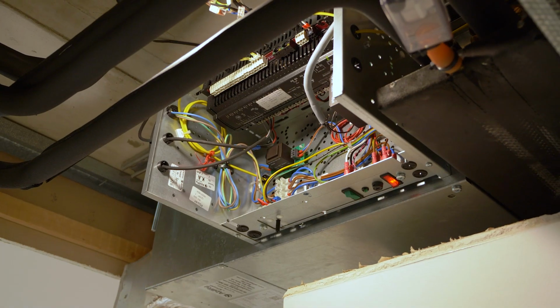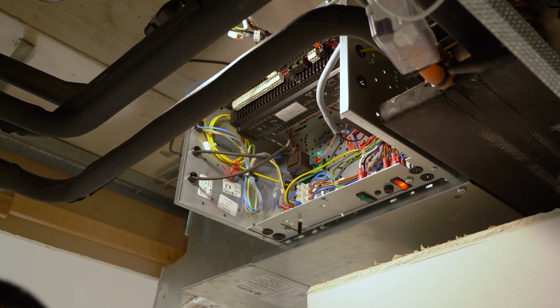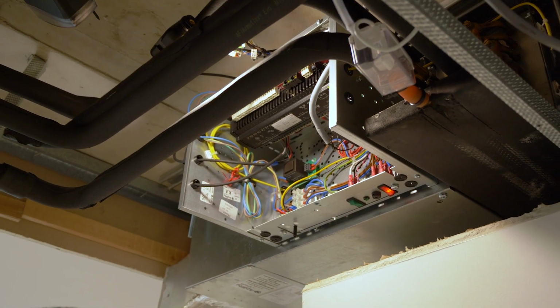One of the obstacles that we encountered on this job was that the old fan coil unit was essentially driven by old 24 volt DC floating valves. This is for the controls people out there. It was simply supplying a 24 volt DC current to the valve, causing it to open and close and float within a position to allow for flow. This is modulating the flow in a crude manner.